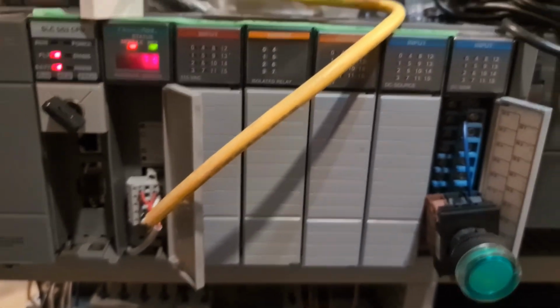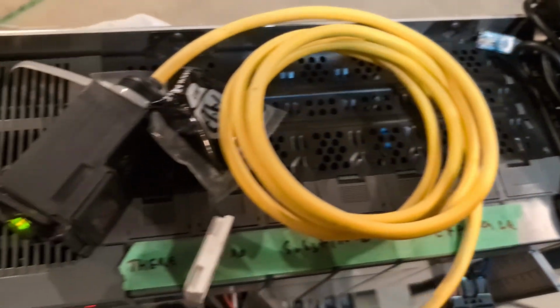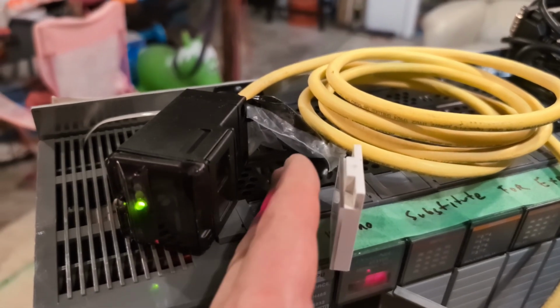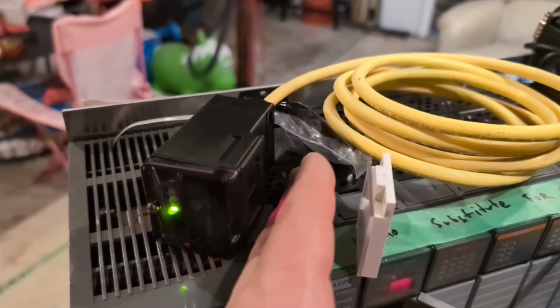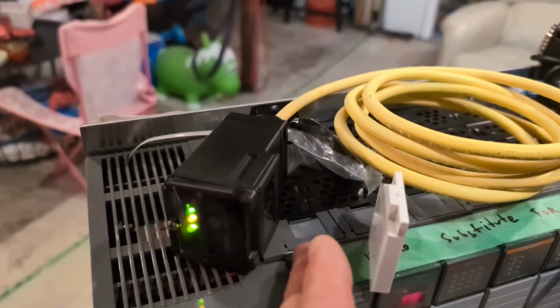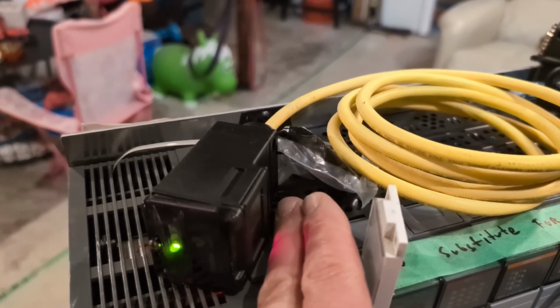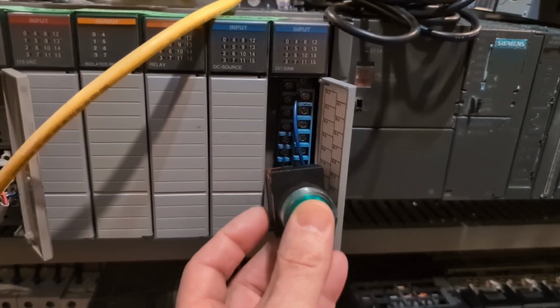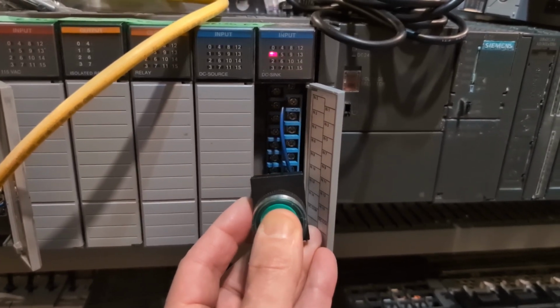Now, let's have a quick look at the DeviceNet network. Beyond the scanner, it also has a retroreflective photo eye, and that blinking LED is indicating that the sensor is not in the scan list. We also have a push button that's wired directly into an input card, nothing to do with the DeviceNet. That's just for a little variety.